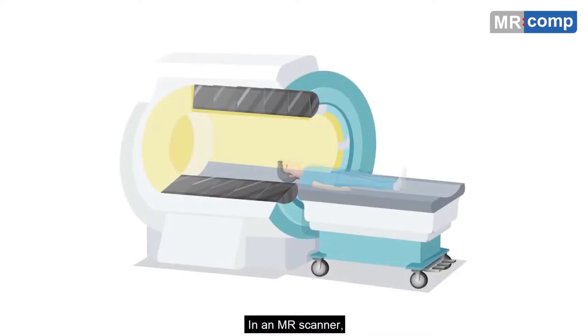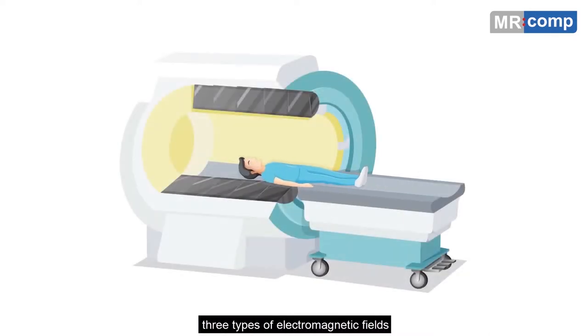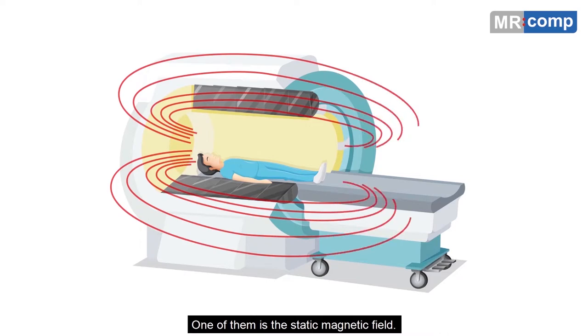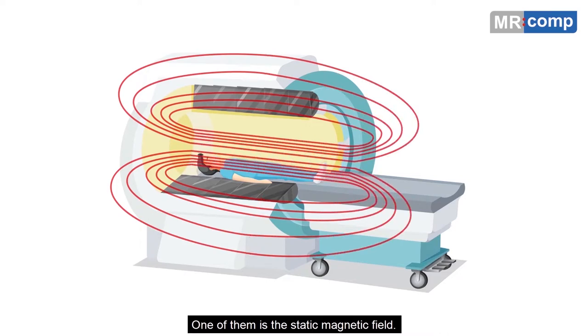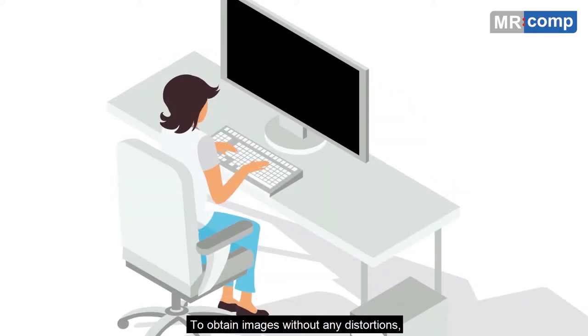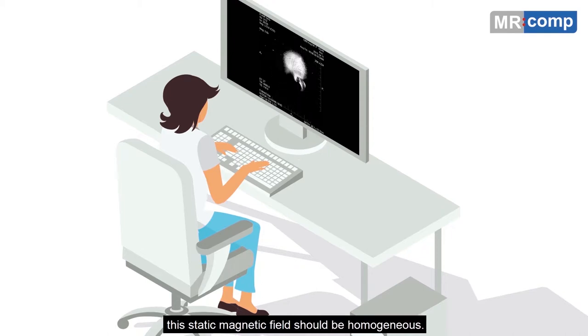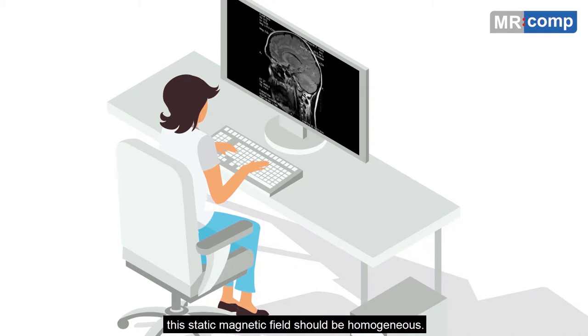In an MR scanner, three types of electromagnetic fields are involved in imaging. One of them is the static magnetic field. To obtain images without any distortions, this static magnetic field should be homogeneous.